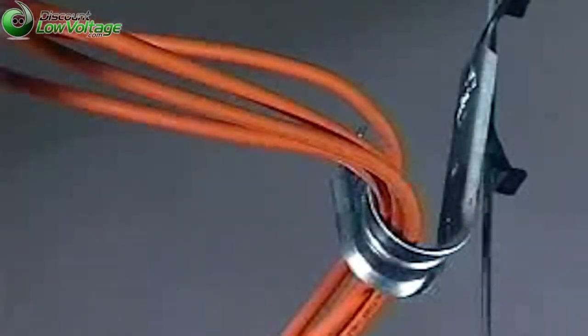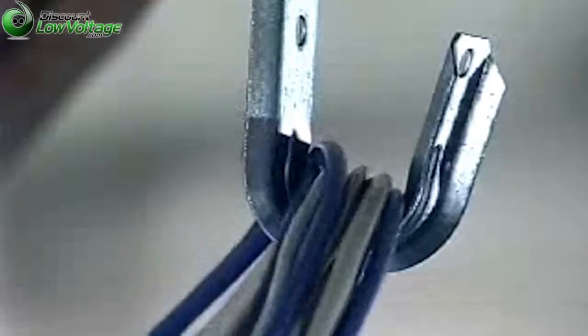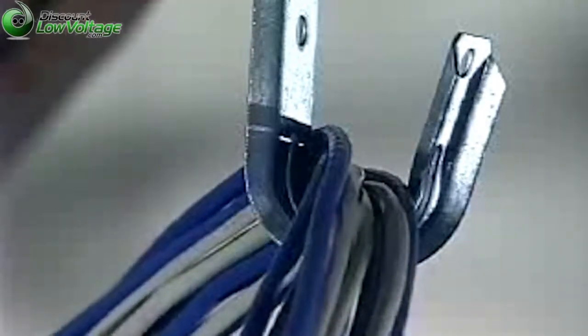The CableCat routes cables so that the cable bend radius is larger than one inch to comply with the TIA 568A standard. The new galvanized finish provides corrosion resistance and makes pulling cables smoother.